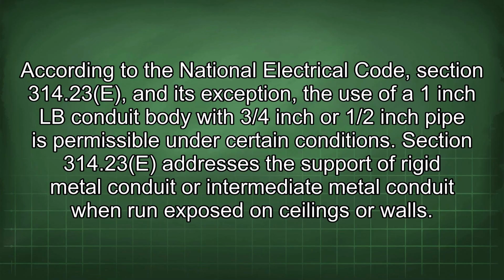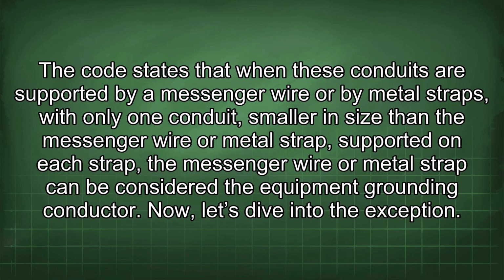According to the National Electrical Code, Section 314.23(E) and its exception, the use of a 1-inch LB conduit body with 3/4-inch or 1/2-inch pipe is permissible under certain conditions. Section 314.23(E) addresses the support of rigid metal conduit or intermediate metal conduit when run exposed on ceilings or walls. The code states that when these conduits are supported by a messenger wire or by metal straps, with only one conduit, smaller in size than the messenger wire or metal strap, supported on each strap, the messenger wire or metal strap can be considered the equipment grounding conductor.